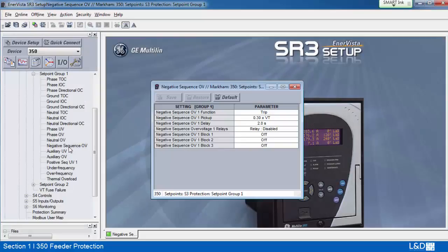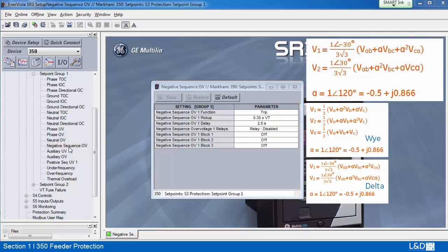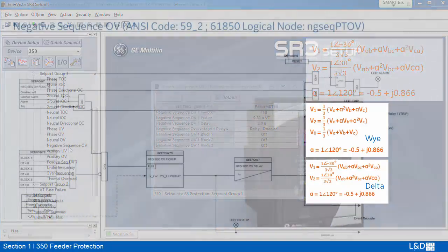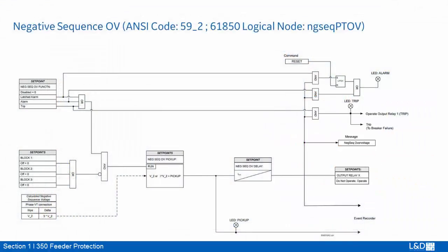Negative sequence overvoltage is the opposite of positive sequence undervoltage. It can be used to detect the loss of one or two phases of a source or reversed voltage phase sequence. The input is the calculated negative sequence voltage using the Fortescue equations. The logic diagram shows the input V2 is used for Y connection and 3 times V2 is used for delta connection.